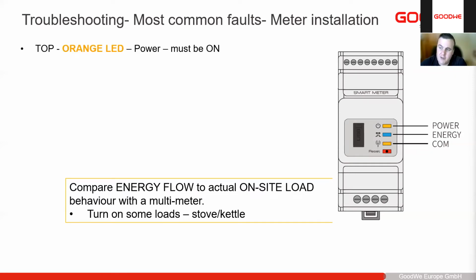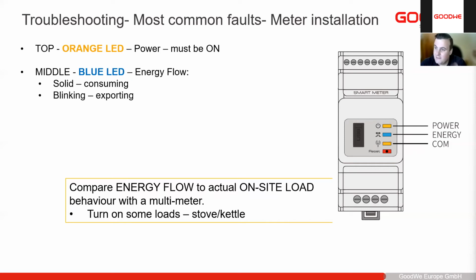The top power obviously needs to be on, so we know the smart meter is on and working. Next we have the blue energy flow. If it is solid, it's consuming from the utility. If it is flashing, it's exporting. So if our inverter is not even on yet, we've just powered up our smart meter and we see that it's flashing, then it's indicating that we are exporting. Then we can already know there's something wrong with our installation. We need to double check to make sure it is correct.